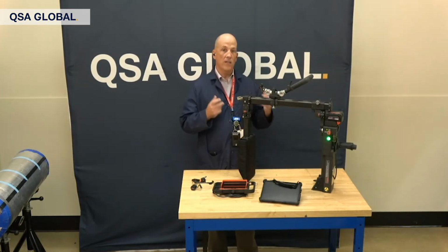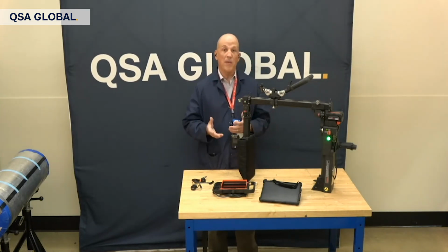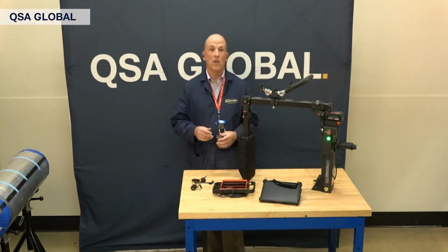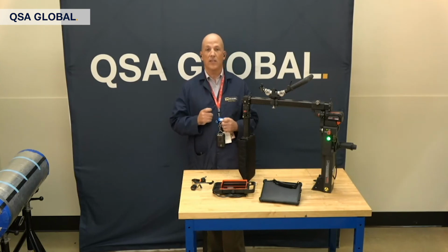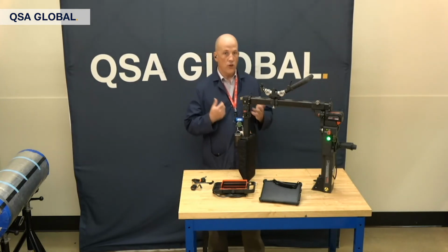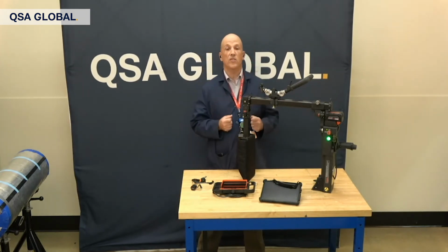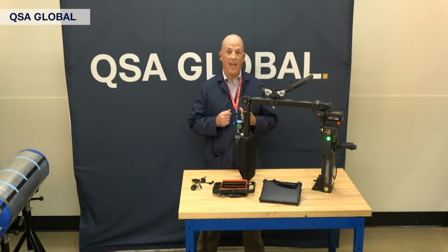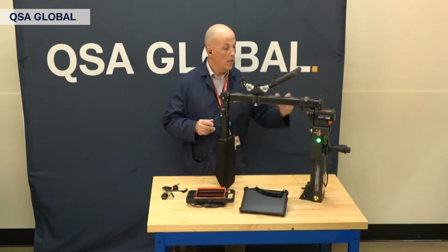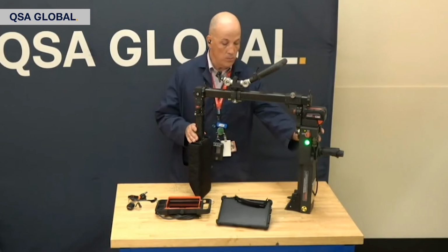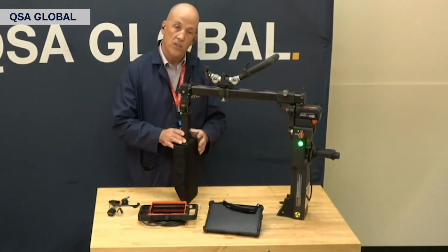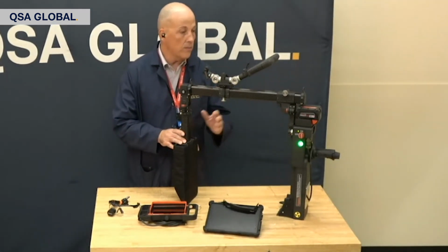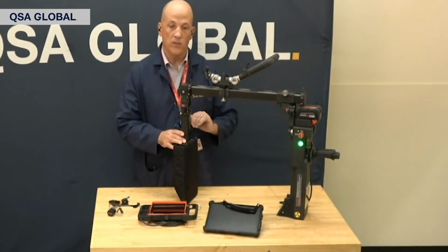It combines real-time radiography with the speed of a handheld system to perform qualitative screening of a lot of insulated piping quickly. The third generation OpenVision system, the OpenVision DX, consists of a 70 kV X-ray tube with a digital imaging detector in a C-arm configuration.